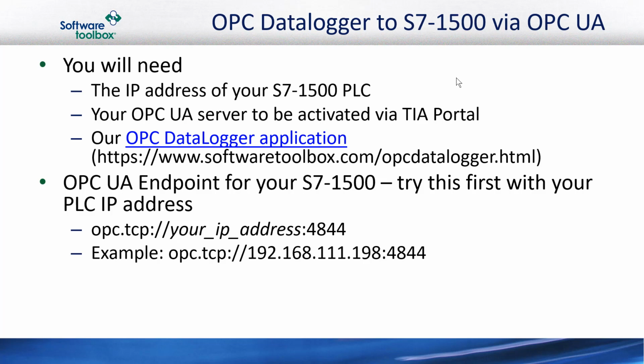Most likely, it's what you see below on the screen, with the example where you would replace the example IP address I've used of 192.168.111.198 with your IP address. The port number 4844 is the default for this S7-1500. So unless someone has changed this in your PLC, this should work.